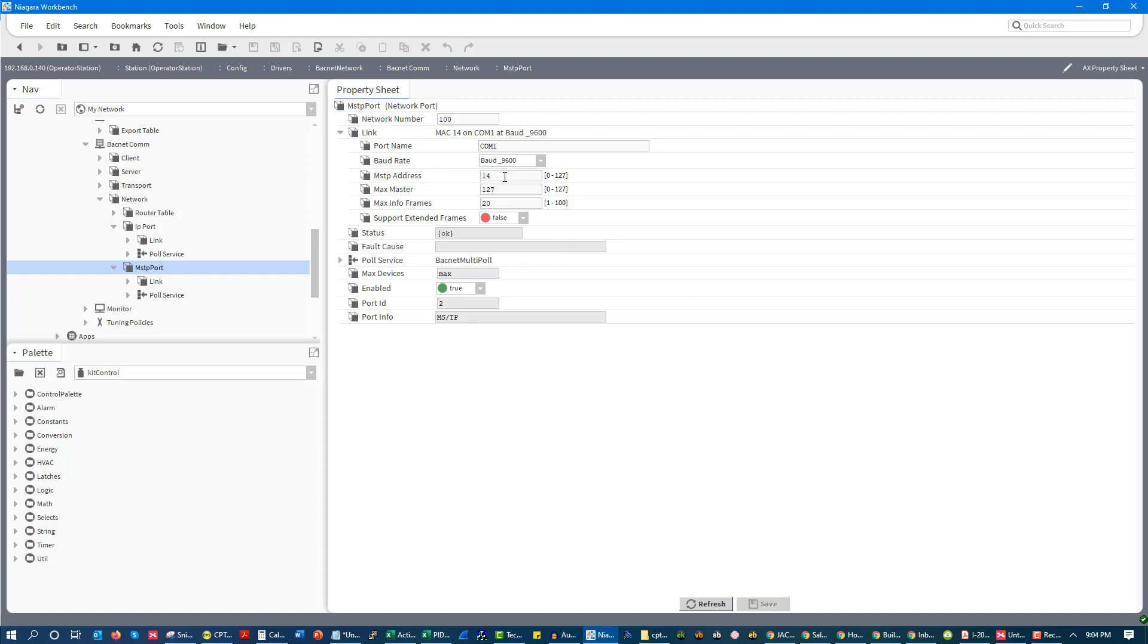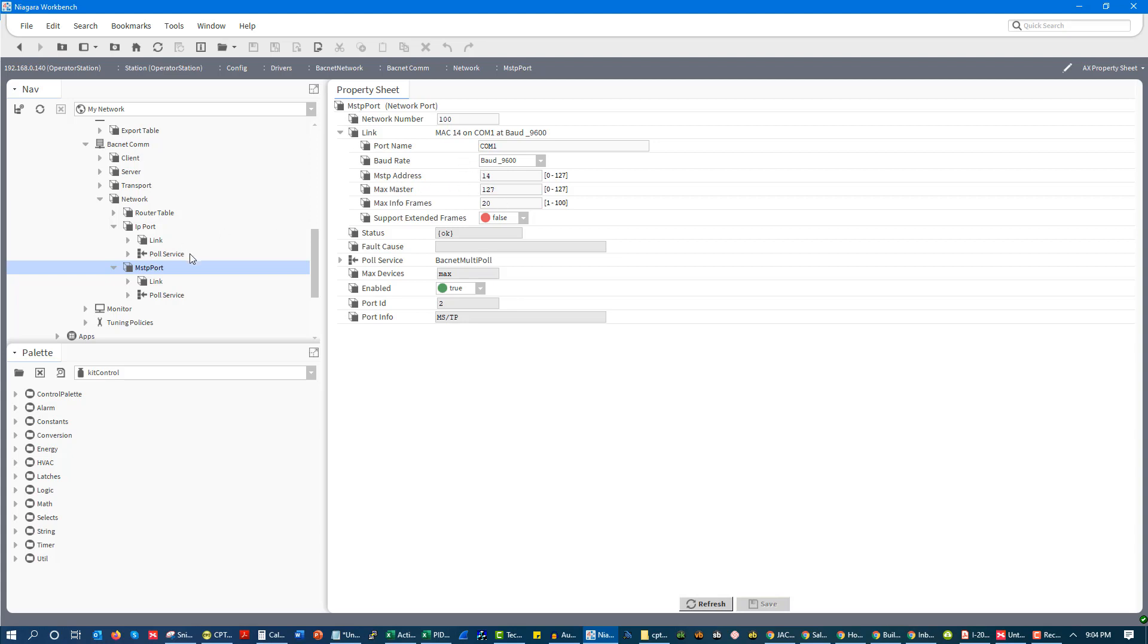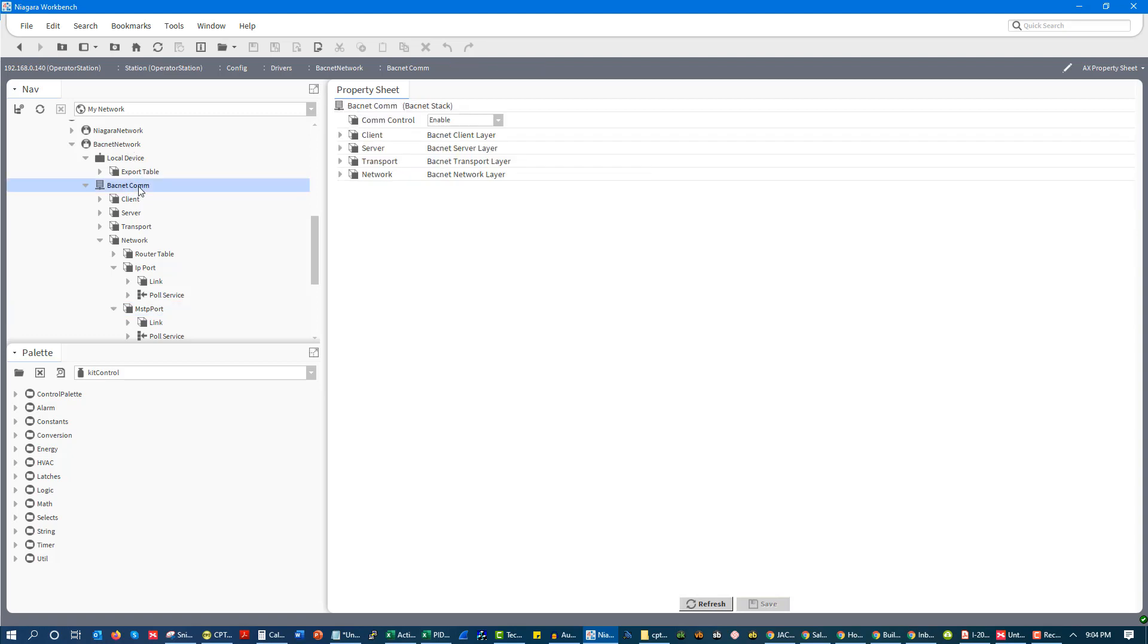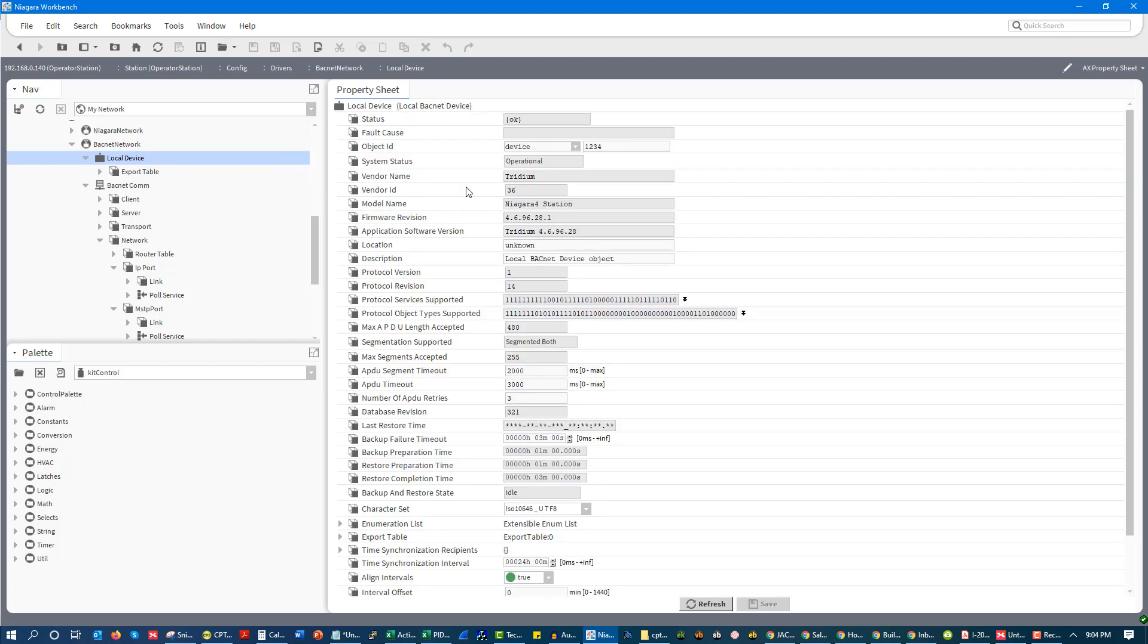You can also have your MSTP addresses, also known as your MAC addresses. These are going to be unique hardware addresses for each controller. So each controller needs to have a unique one. And we're also going to have devices. So we're going to have our device IDs. So if we go to our local device here, we'll see we have a device ID here. It's got to be a unique device ID. You don't want to have device ID conflicts.